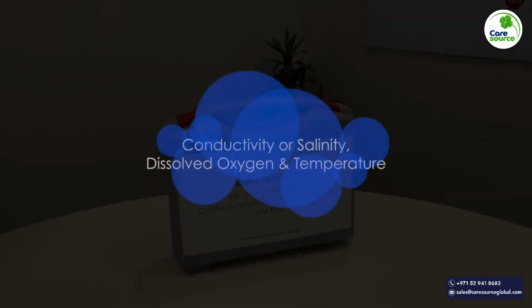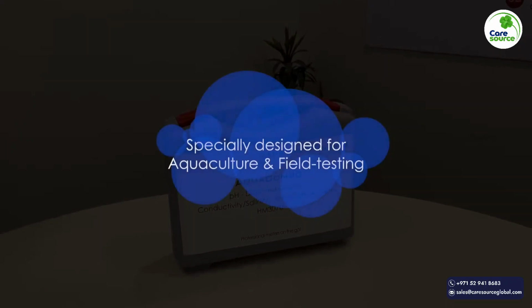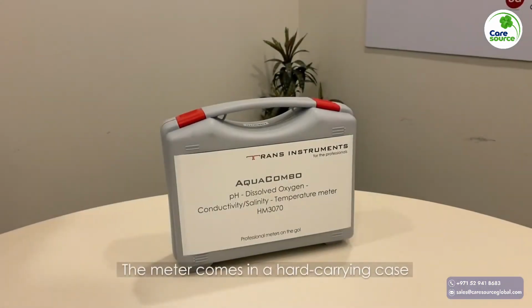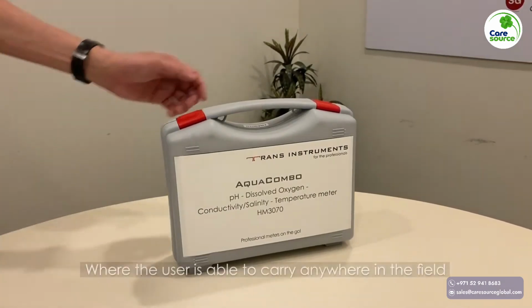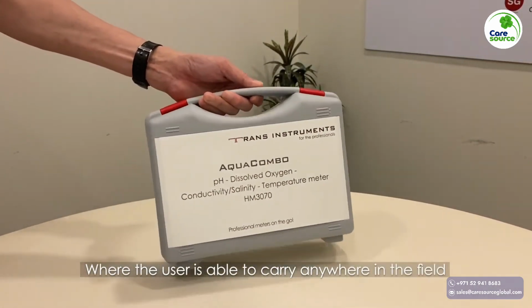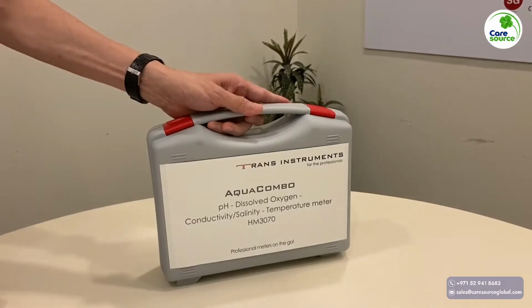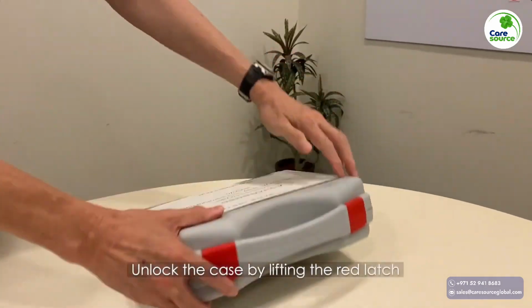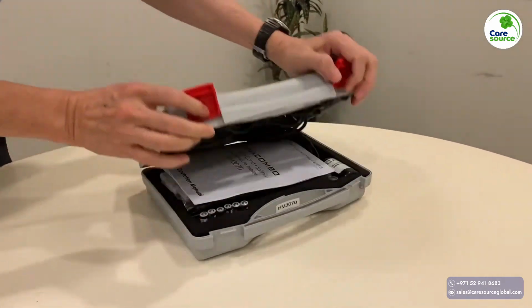Features 4-parameter measurement of pH, conductivity or salinity, dissolved oxygen and temperature at one go. This meter is specially designed for aquaculture and field testing. The meter comes in a hard-carrying case, where the user is able to carry it anywhere in the field. Unlock the case by lifting the red latch.